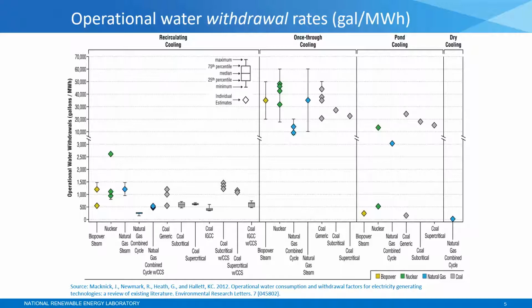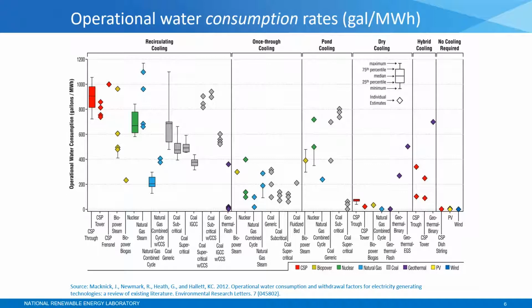Now let's look at water consumption. Here the trends flip: whereas once-through cooling withdrew a lot more water than recirculating cooling, once-through cooling actually has a lower consumption rate than recirculating cooling. This is because cooling towers operate primarily through evaporation, and almost all the water they withdraw, they end up consuming. So we see higher levels of water consumption, anywhere from 1.5 to 2 to 3 times more, for recirculating cooling than for once-through cooling technologies.